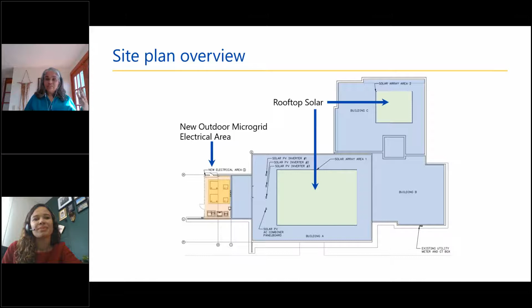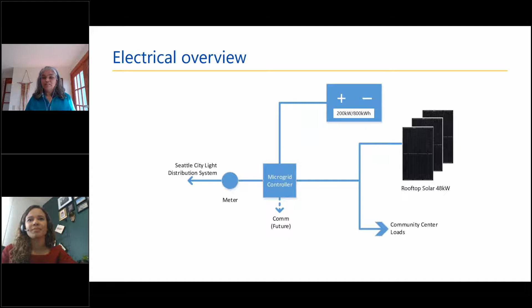So as I've described, it's a pretty simple schematic. We take the existing community center loads. They're fed by either the battery or the solar, and the microgrid controller is the device that makes sure that in islanded mode, everything stays connected and served, and during non-islanded mode, it's operating directly connected to the grid.